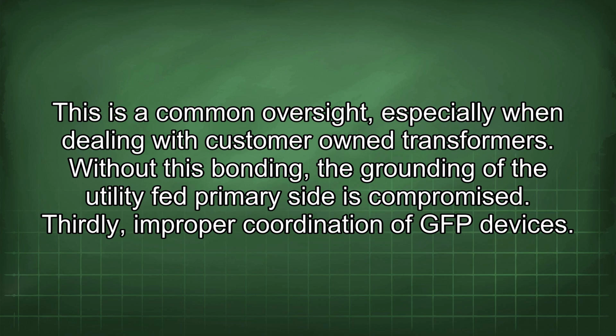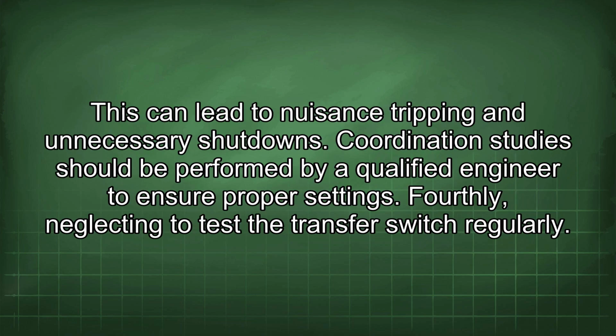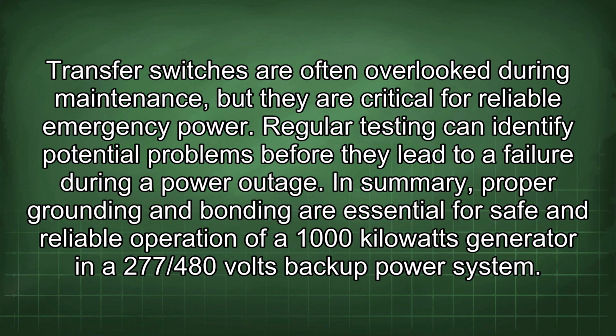Thirdly, improper coordination of GFP devices. This can lead to nuisance tripping and unnecessary shutdowns. Coordination studies should be performed by a qualified engineer to ensure proper settings. Fourthly, neglecting to test the transfer switch regularly. Transfer switches are often overlooked during maintenance, but they are critical for reliable emergency power. Regular testing can identify potential problems before they lead to a failure during a power outage.